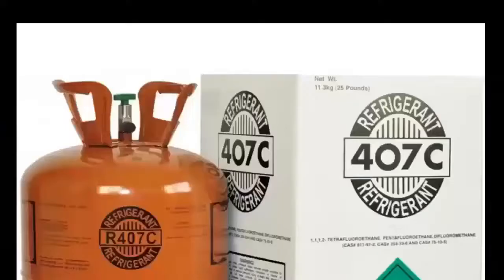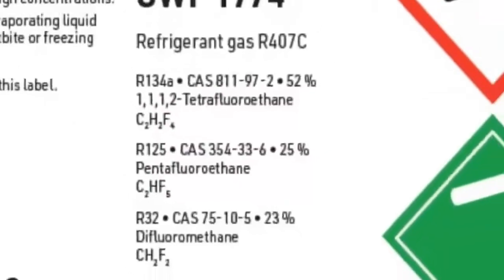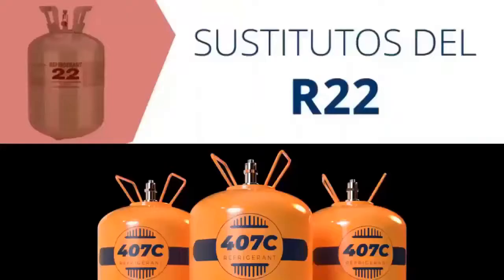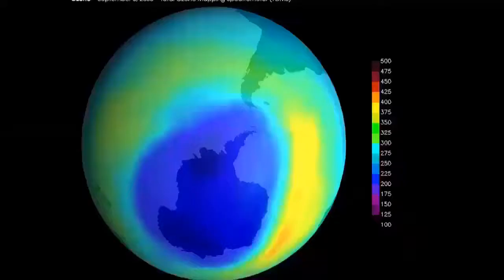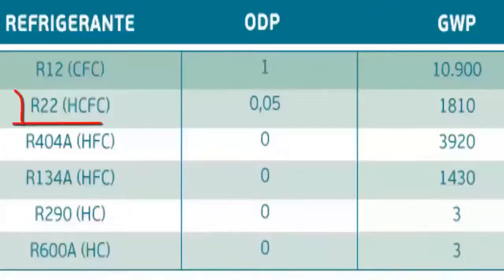R407C is a mixture made up of R32, R125, and R134A gases, with properties including pressure, capacity, and efficiency that are extremely similar to those of R22. It is precisely this similarity that makes R407C used as a replacement for R22, both in equipment already in service and in new systems. Let's remember that R22 must be replaced because it destroys the ozone layer.